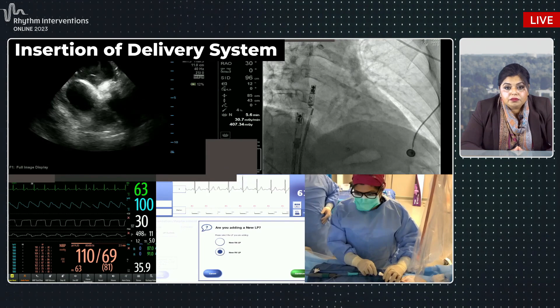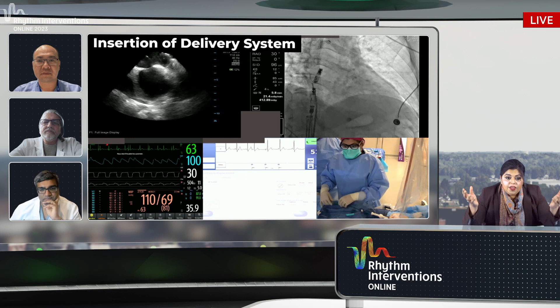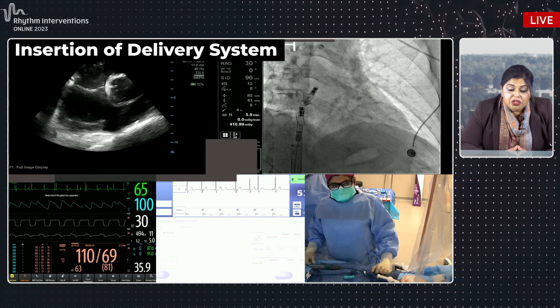Again, one of the differentiating features of this leadless device is that you can turn on therapies at this point. So you can actually program it to VVI pace, and you can actually pace while you implant if you need to. Hopefully you don't have to, and it's not recommended, but if you did have to and you did knock out the bundle on the way in, you could. But here we are getting ready. The device is now ready to be covered back up once we program it.